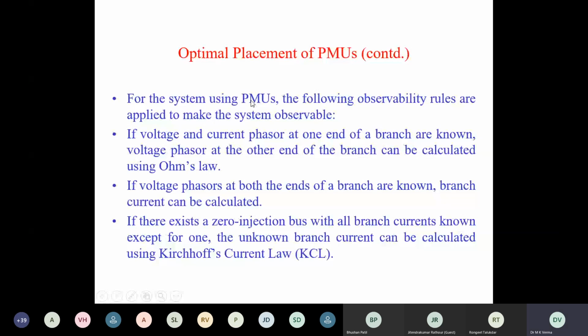With this, he obtained the location of PMUs for the IEEE 14 bus system, the NRPG 246 bus Indian practical power system, and the New England 39 bus system. Three systems he considered. These were the observability rules used to obtain the optimal location of PMUs, avoiding the use of PMUs at all locations. The voltage and current phasors at one end of a branch are known, so the voltage phasor at the other end can be calculated using Ohm's law. So if you put a PMU at one bus and the other bus is connected to it through a certain branch, there is no need to put a PMU at the second bus because that voltage can be calculated by Ohm's law.